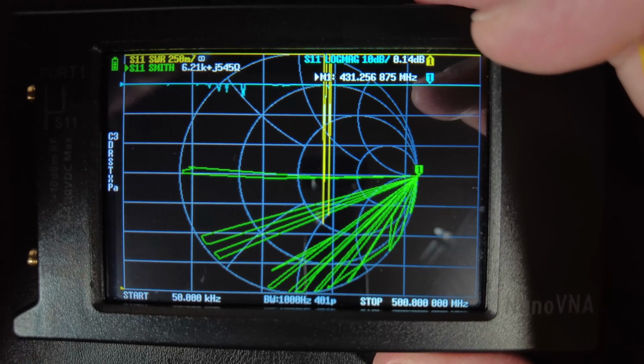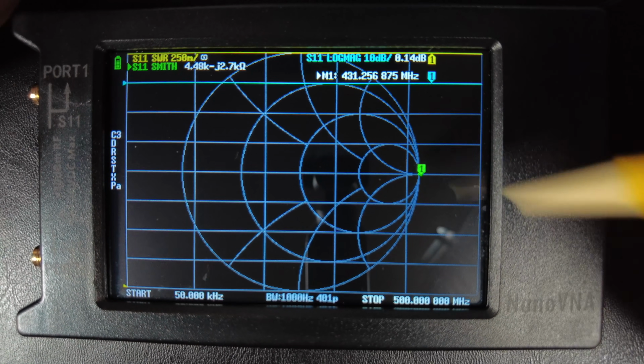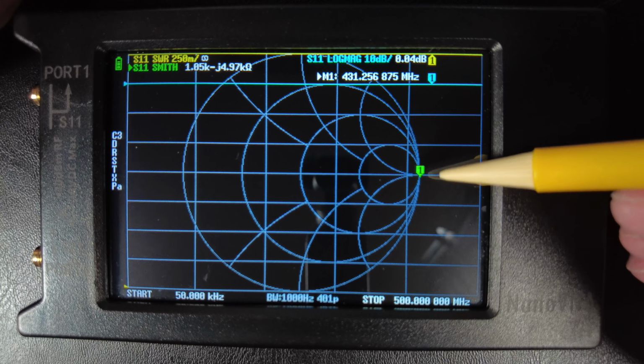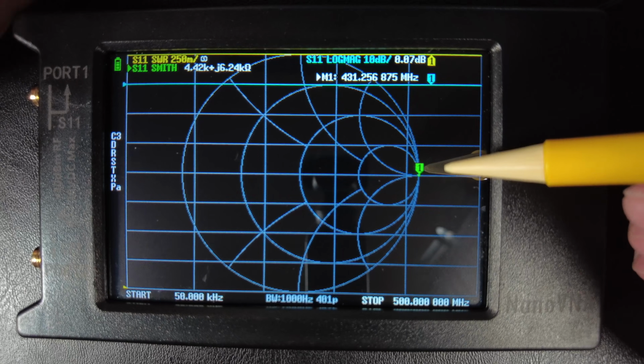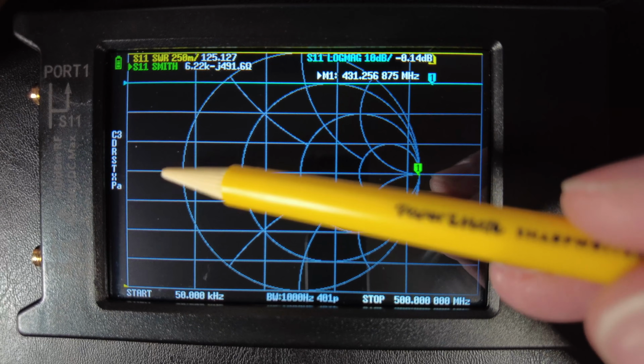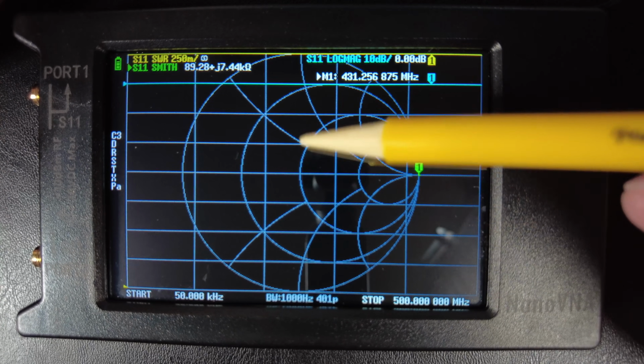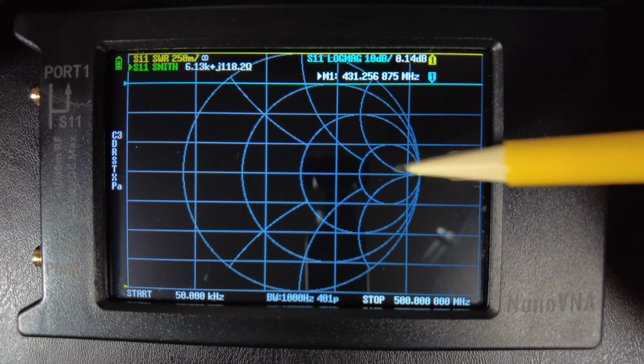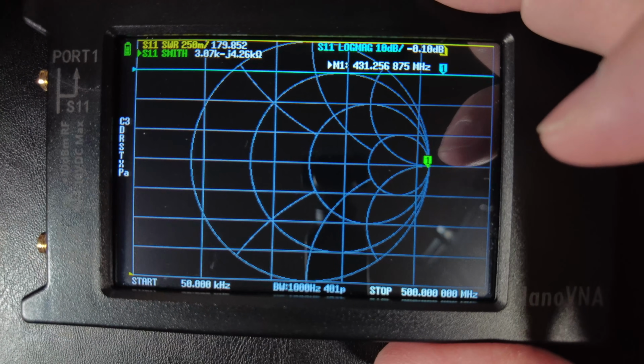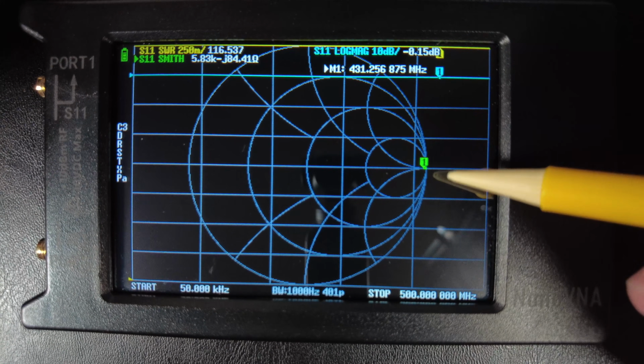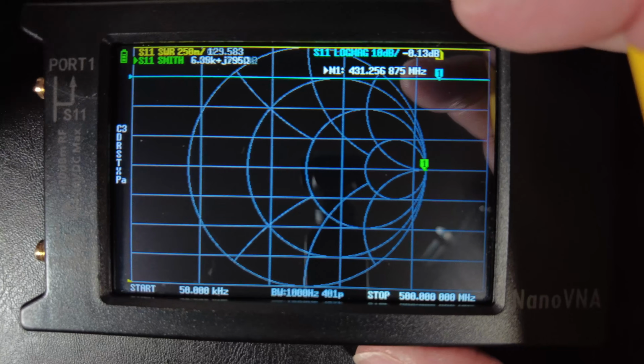And if you ever want to check your calibration, if you have the Smith chart being displayed, an open will put a marker here all the way on the far right. A short will put one all the way on the far left. And the 50 ohm load should land right in the middle. So here now that there's nothing connected to port 1, we see the markers all the way over to the right.